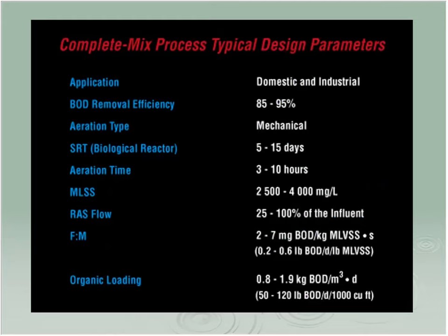My process ran somewhat on that, but again, 85 to 95% BOD removal, piece of cake, 5 to 15 days, same stuff. Not much variation here, really. They're stretching out the F/M a little bit to 0.6, but all of that's a typical range for these systems.